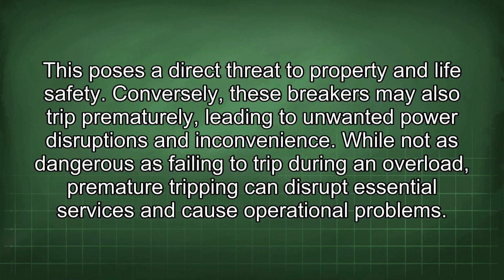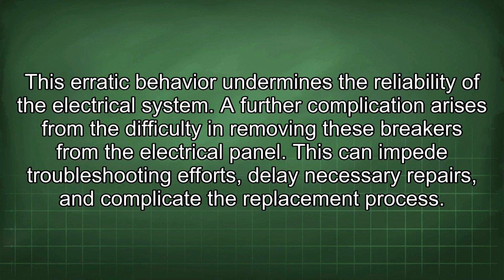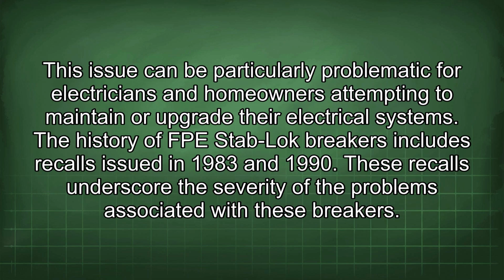Conversely, these breakers may also trip prematurely, leading to unwanted power disruptions and inconvenience. While not as dangerous as failing to trip during an overload, premature tripping can disrupt essential services and cause operational problems. This erratic behavior undermines the reliability of the electrical system. A further complication arises from the difficulty in removing these breakers from the electrical panel. This can impede troubleshooting efforts, delay necessary repairs, and complicate the replacement process. This issue can be particularly problematic for electricians and homeowners attempting to maintain or upgrade their electrical system.